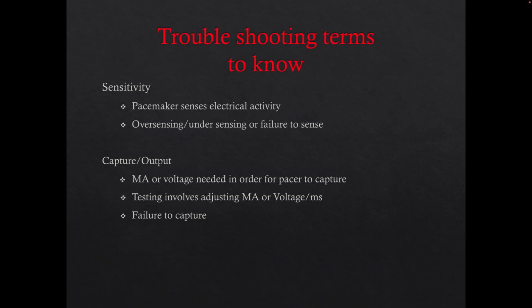So sensitivity is what it senses. What is it picking up? What's the signal? Does it pick up the P wave? Does it pick up the QRS, the atrial or ventricular response? So the pacemaker senses electrical activity, and there are things called oversensing and undersensing. Oversensing would be that it thinks it sees something that's not there. For example, I mentioned earlier, electrocautery, that could be picked up, right? The device thinks that it sees something and it doesn't give an output. Could be a really bad situation because maybe the patient's got complete heart block and it doesn't deliver a capture.